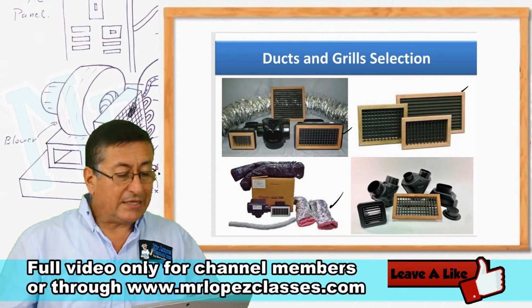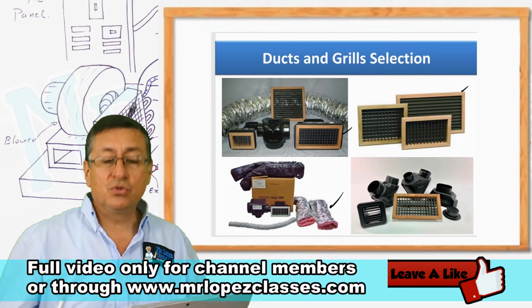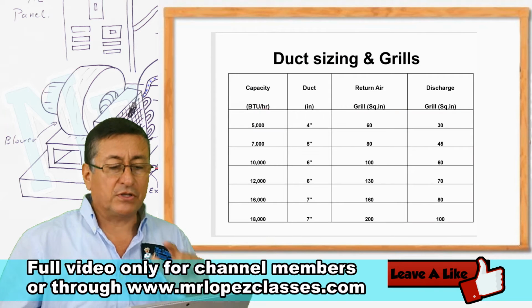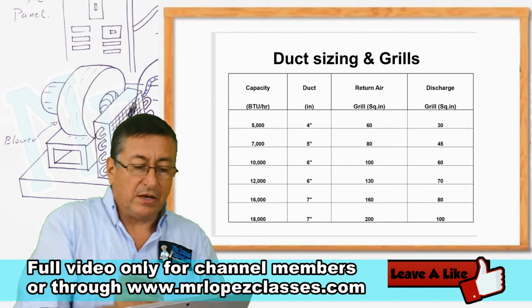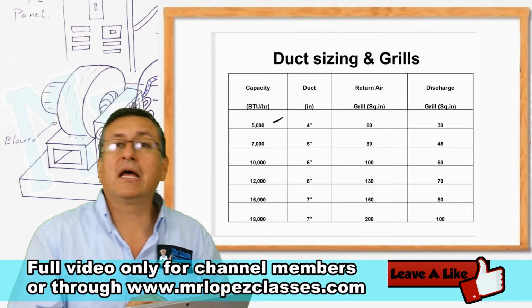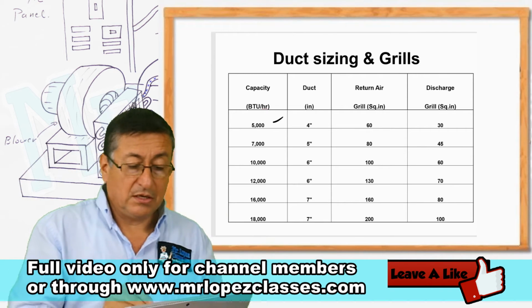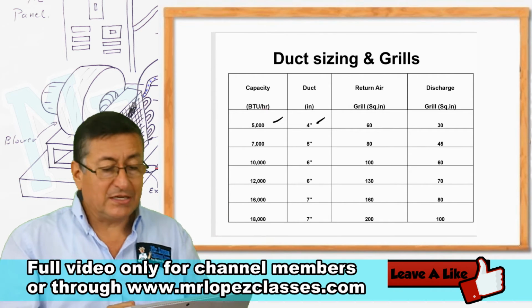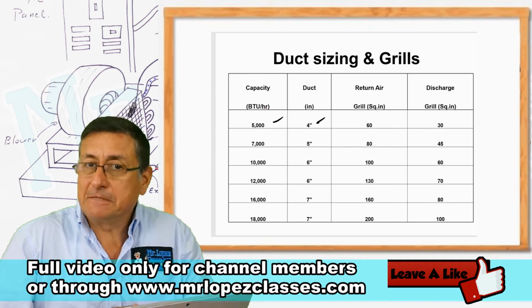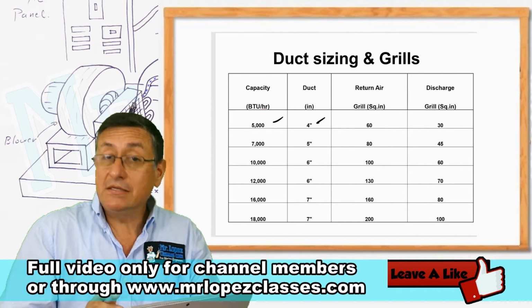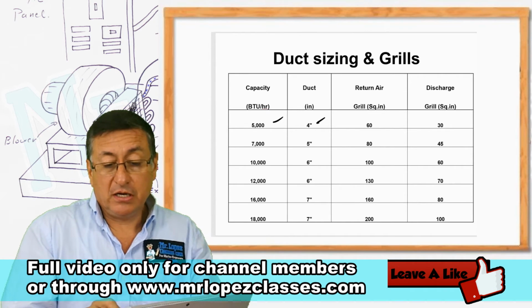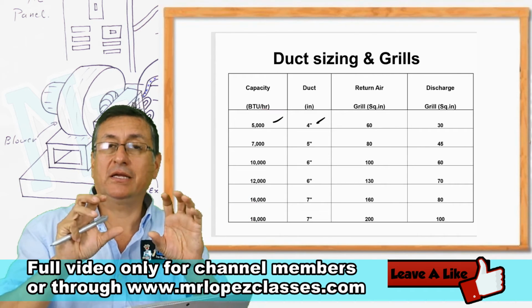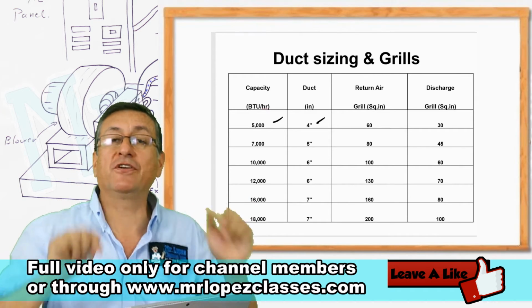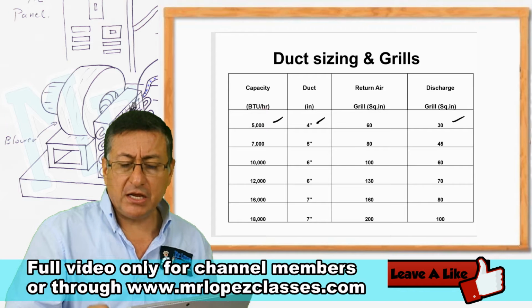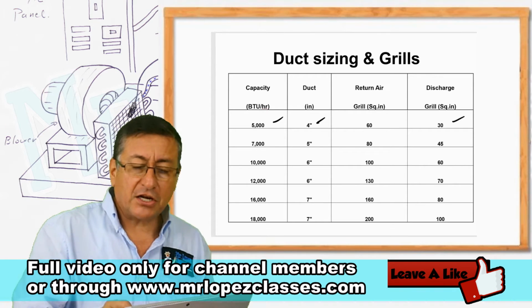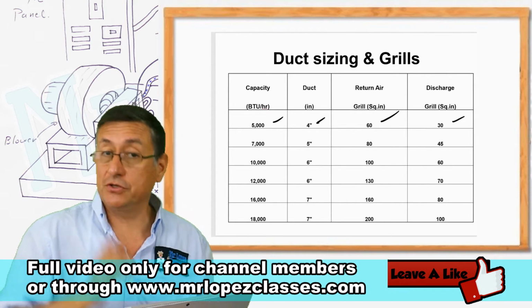And this is the chart to select those ducts. This information is very important. For example, this one, for 5,000 BTUs, I need a duct of 4 inches in diameter. And the grills for that specific duct, the discharge grill, the grill that discharges the fresh air, should be 30 square inches, and the return 60 square inches.